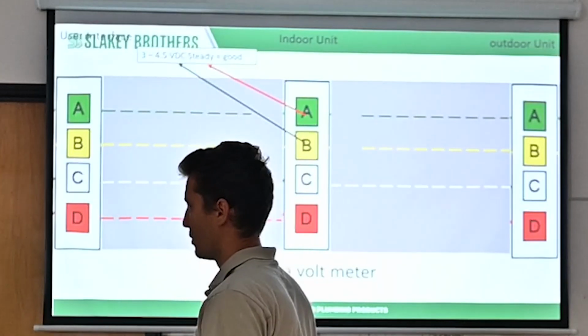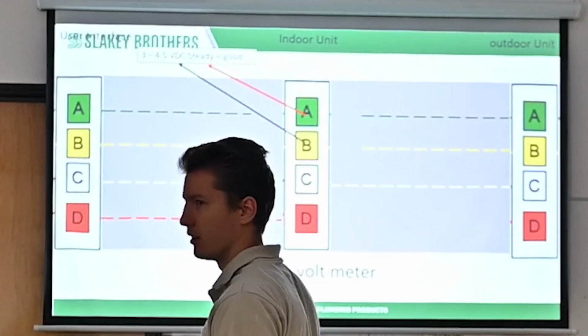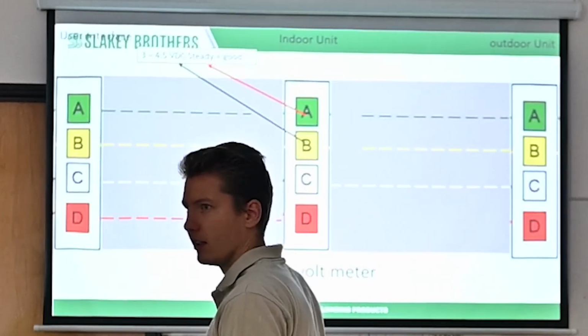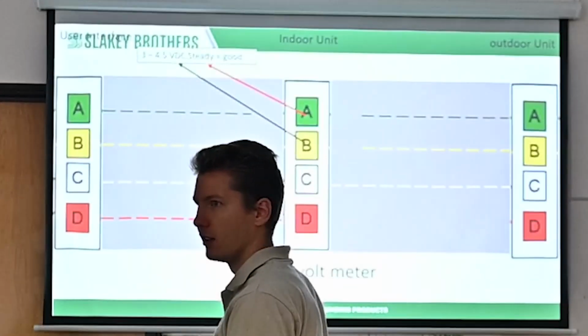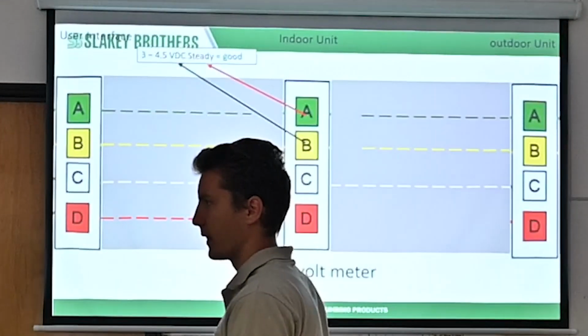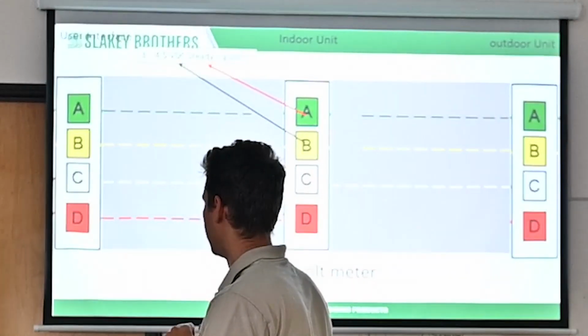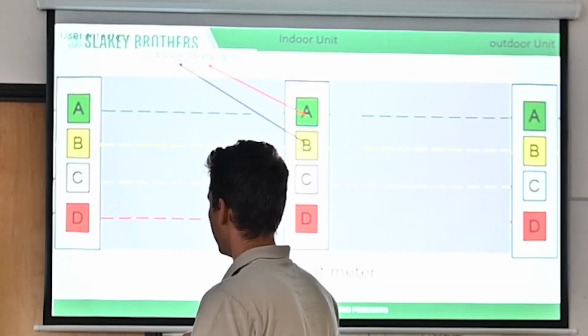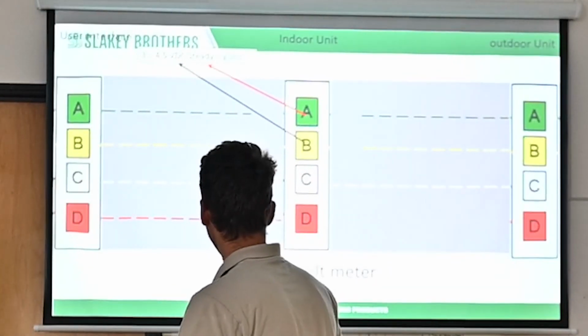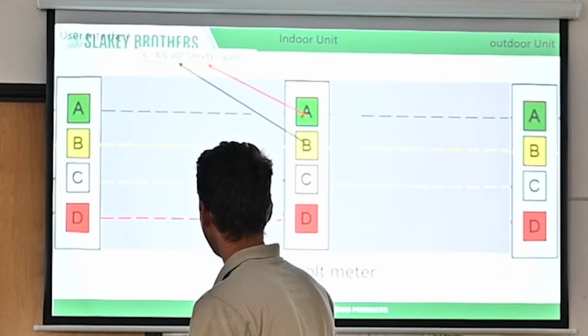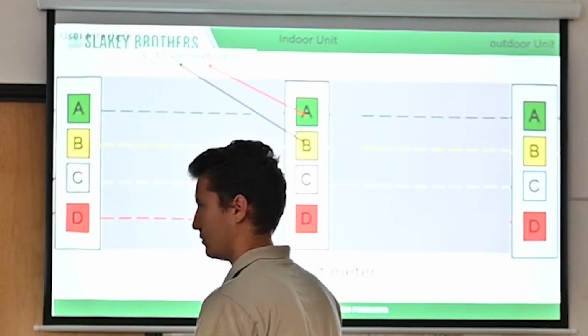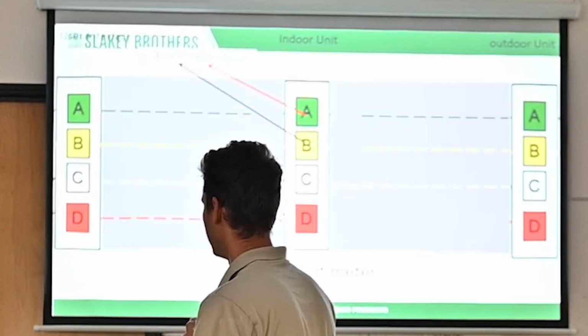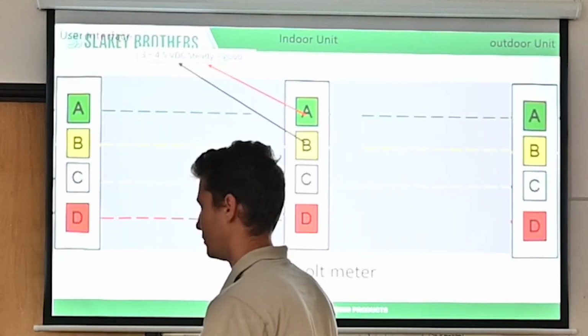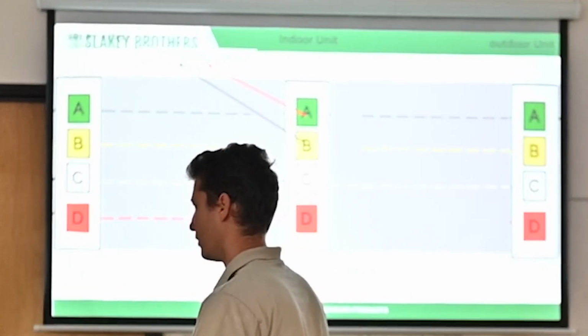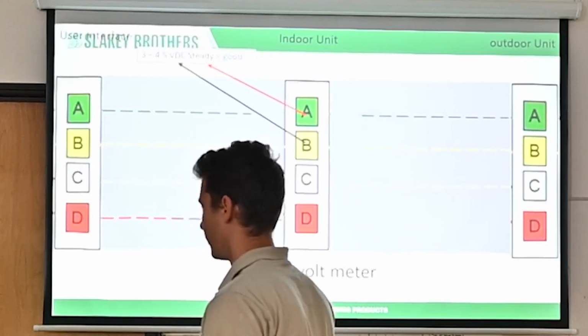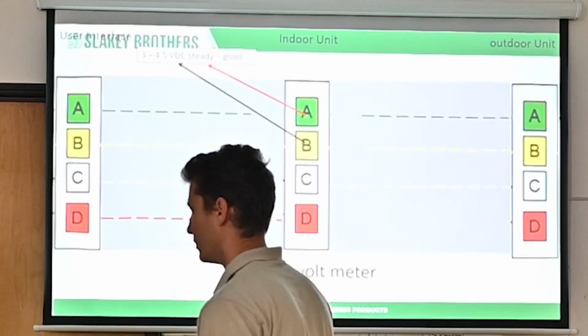I don't know what it was. I don't know either. Are we talking about miscommunicating between high and low voltage, right? No, it's not like running one wire, two wires together. We're talking about the communication line right here, where it's using that DC signal to tell the unit itself what it's doing. It'll pick up interference, and in my scenario, my wire looked good. I don't know why it was not handling it. I put a new wire in and it started working. I'm like, I don't know.